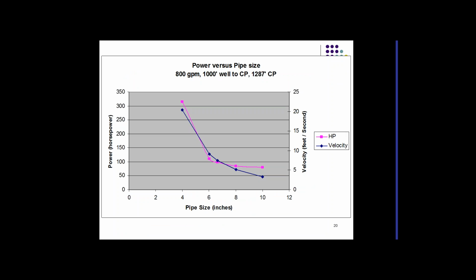So how does the velocity of the water going through the pipe affect this? Here's about 7.5 feet per second. When I get above 7.5 feet per second, my energy requirement increases rapidly. So I need to keep the velocity of the water in the pipe below 7.5. Typically they're designed at 5, but if you make a change to it, it may increase that velocity. As the velocity goes up, the friction losses also increase in the pipe. So keeping it below 7.5 is an advantage in that regard.